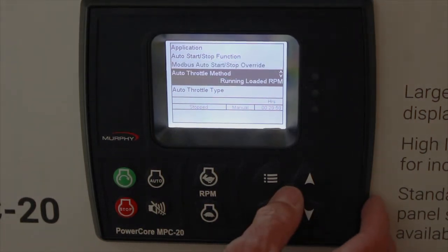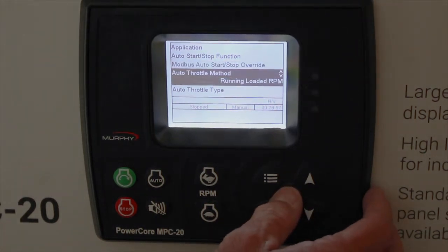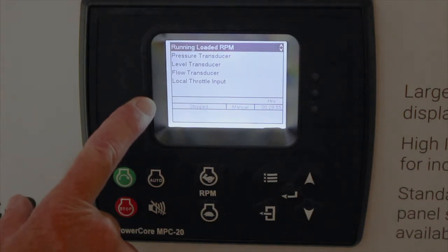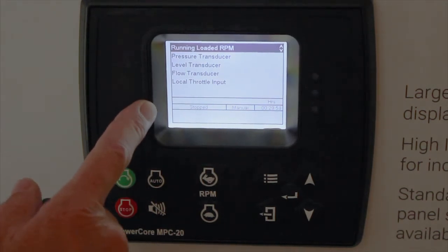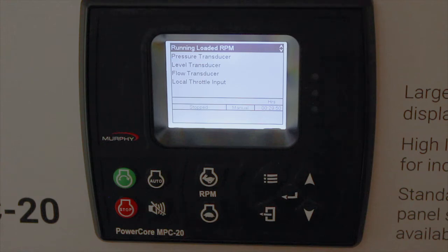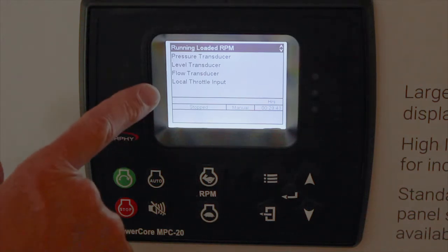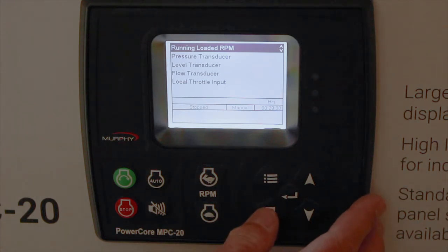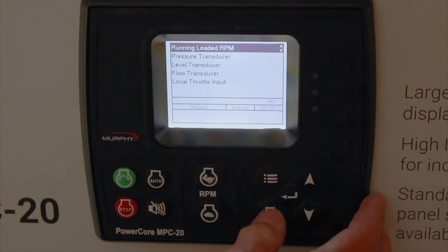Auto throttle method — running loaded RPM is the default. You also have pressure transducer, level transducer, flow, and local throttle input. Pressure, level, and flow maintain a value for throttling between minimum and maximum RPM set points. Local throttle input uses an analog input — we throttle proportionally between minimum and maximum RPM set points, treating it simply as a percentage regardless of what it represents.